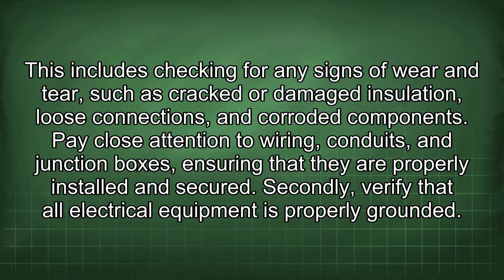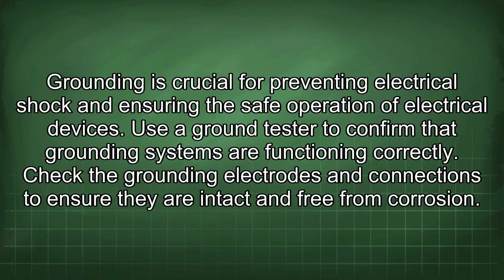Secondly, verify that all electrical equipment is properly grounded. Grounding is crucial for preventing electrical shock and ensuring the safe operation of electrical devices. Use a ground tester to confirm that grounding systems are functioning correctly. Check the grounding electrodes and connections to ensure they are intact and free from corrosion.